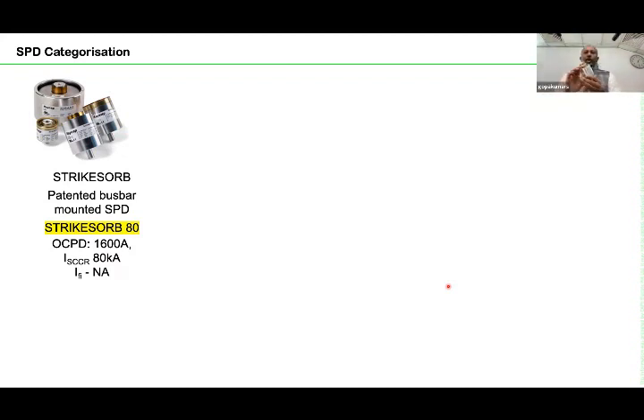The one which I am showing you is an SPD, but it does not look like a conventional SPD. This is a bus bar mounted SPD. The advantage of this SPD I will explain later. This SPD, between line and neutral, you can connect directly on the bus bar, and the energy handling capacity is very high. This is one SPD, not four, one SPD.